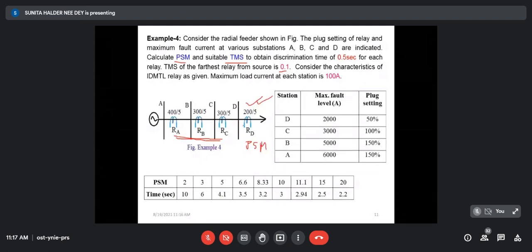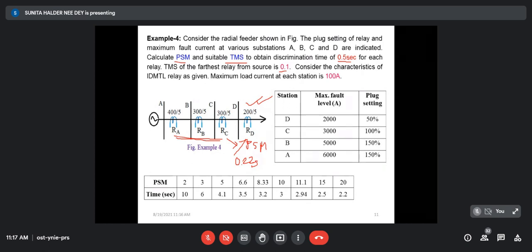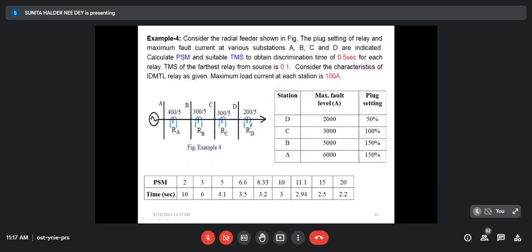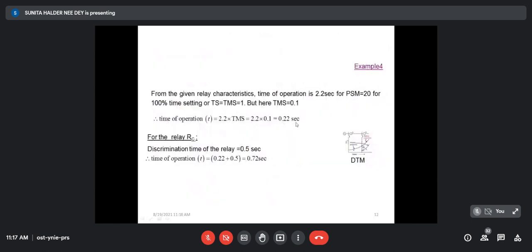RC will be the backup protection of RD. The relay at station C will provide backup protection to station D with a discriminating time of 0.5 second. If relay D is operating at 0.22 second, then RC as a backup relay should operate 0.5 second later — that means at 0.72 second. So for relay RC configured as backup relay for station D, we have to set the PSM and TMS such that it operates at 0.72 second.